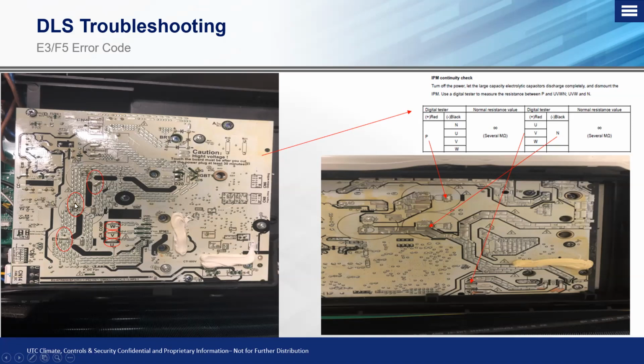Not only are your capacitors okay, but so is the path from the capacitors. I shouldn't say filter, but essentially they store and release charge to help keep that power, that sine wave, consistent, so we have smooth, clean, consistent power, not only to the compressor, but to the fan motor too. As those of you that have attended other classes that I've done, whether it's a basic install class or an advanced troubleshooting class, know, the name of the game, whether it's ductless or VRF, is smooth, clean, consistent power.